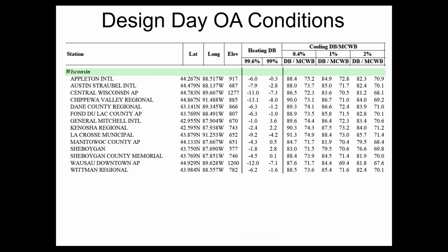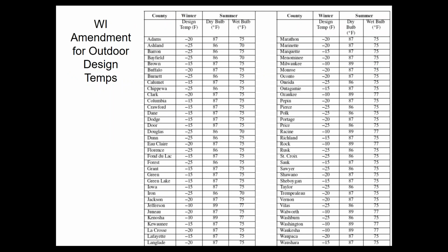Wisconsin, if you are at Milwaukee, which would be Mitchell, it's -1 on the heating side, and 89 or 86 on the cooling side. However, once again, for Wisconsin, there's a special amendment. So you ignore the ASHRAE numbers and you use the amendment, which means in Milwaukee, it's -10 heating, 89 cooling. So if you're using typical software tools, you will need to stop using the defaults of the geographic locator on your software and instead dial in these numbers.